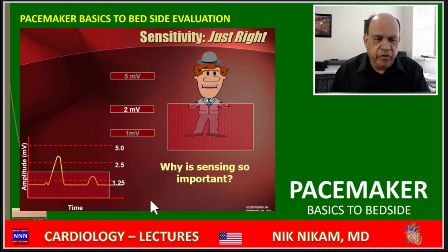We have to program this so it knows the electrical impulse is coming from the atria. Since the voltage varies from atrial to ventricular activity, we have to set the sensitivity of a lead to just detect the atrial activity. That's where sensitivity comes into play.